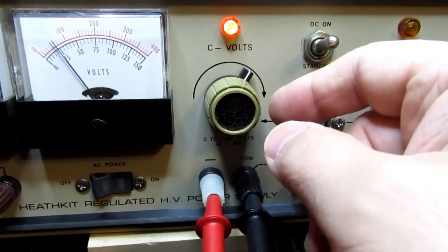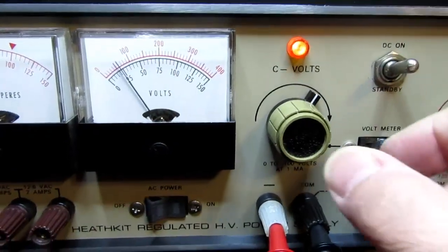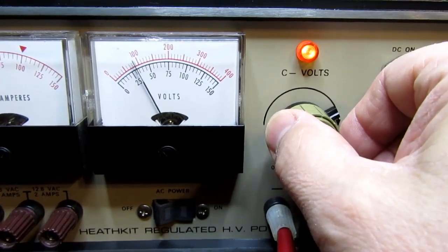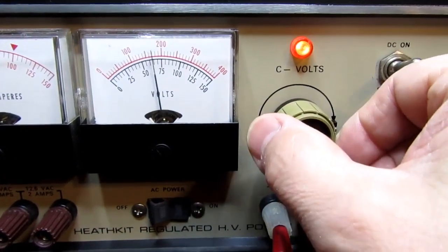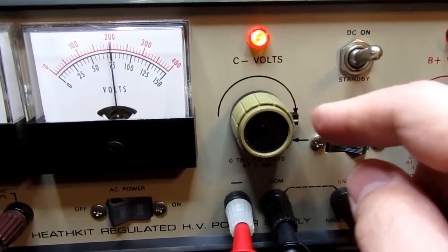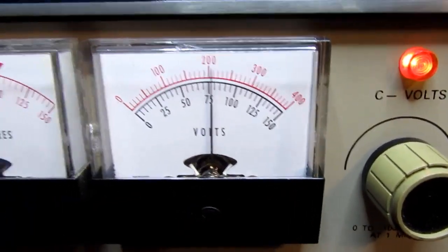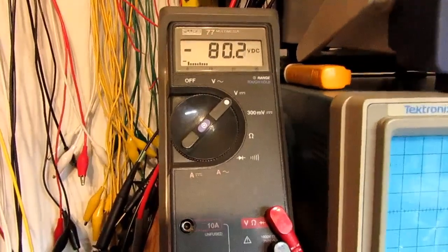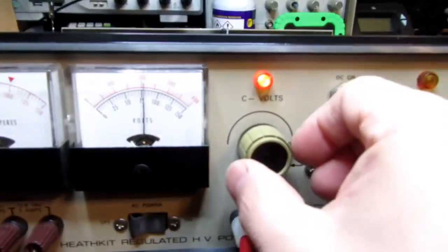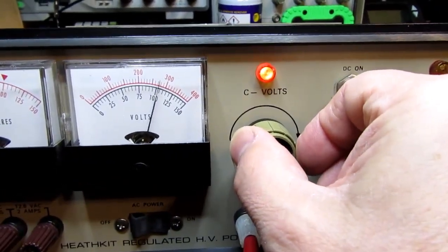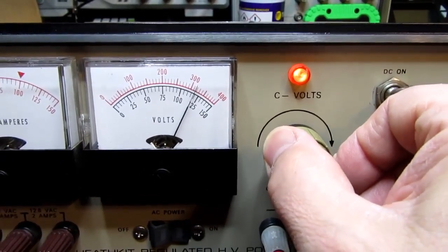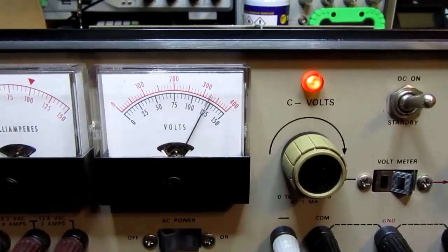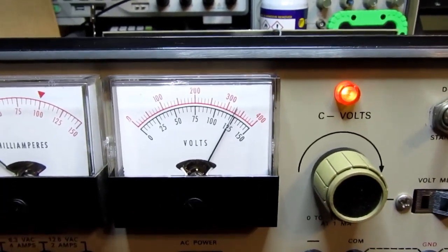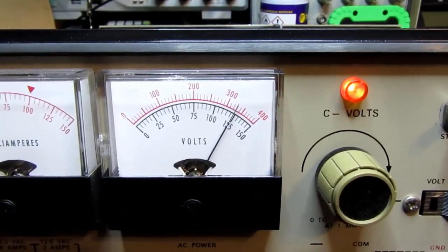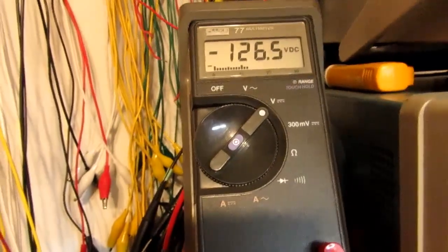So now the rest of this rotation should take me all the way up to 150 volts. I'm over here at about the 3 o'clock position. We're up to 75 volts. And it's reading about 80. And then a little bit more rotation takes me up, you know, somewhere in the ballpark of 125 volts. It's really only rated to 100 volts. Anything extra you get out of it's a bonus. So it's reading about 125 volts there.